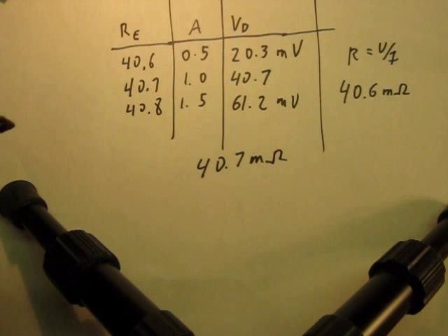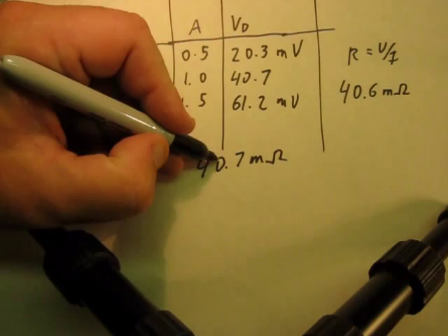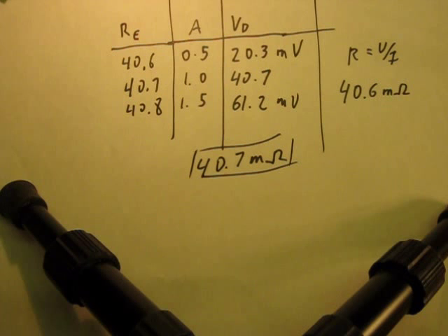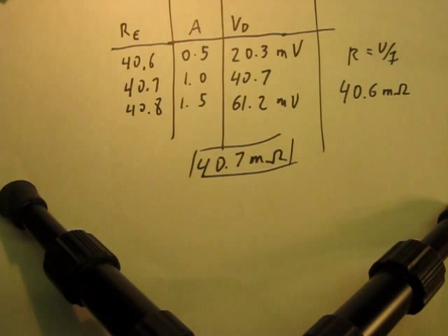But that makes a lot of sense. If you take a look at a meter basically, it's always a small piece of wire inside the meter, and we'll take a look at that in a second. So basically what happens is anytime you put this Fluke 17B on the 10 amp range into a circuit, it's basically putting a 40.7 milliohm resistor. Now that doesn't sound like a lot, but you're kind of into the resistance of batteries, and all of a sudden if you're doing kind of high amp, 5, 10 amp measurement work, this voltage can be quite significant.